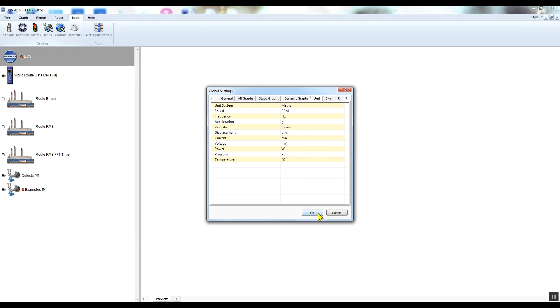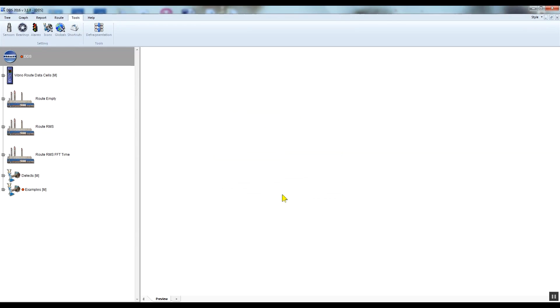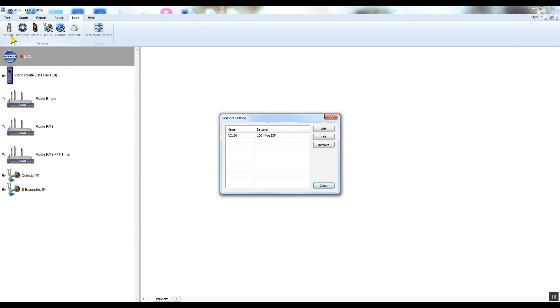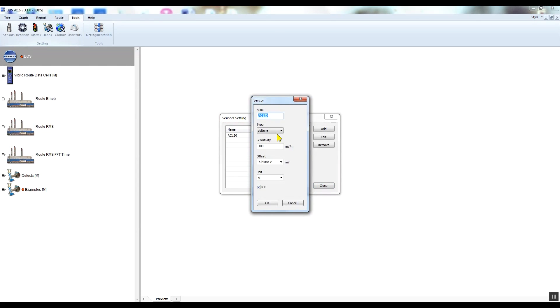To change the sensor sensitivity, click sensors, double-click on the sensor line to open the window where you can change the type or the sensor sensitivity. A standard 100 millivolts per g acceleration sensor type AC-150, which is supplied with the Vibrio M kit, is predefined already.